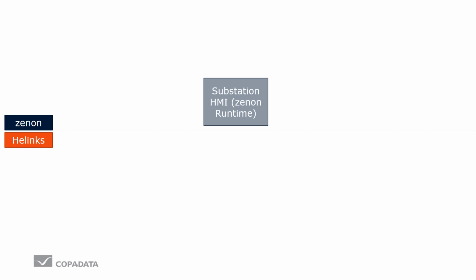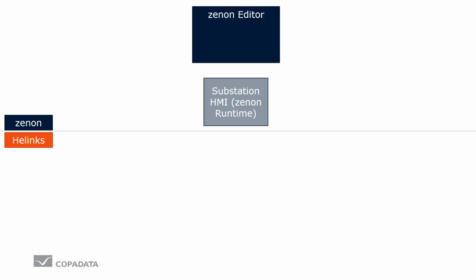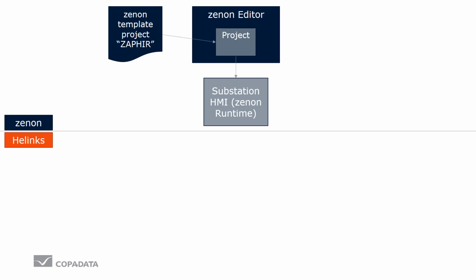So in detail, the process which we found out which fits best looks like this. We are using Zenon, and as a system configuration tool, we are using Helinks. What we want to have is this substation HMI, which is actually the Zenon runtime. We need a Zenon editor to load a project into the Zenon runtime. But this project needs to be configured. So first of all, what we learned in the previous slide, we want to have this template project, which provides us the usability of the project.